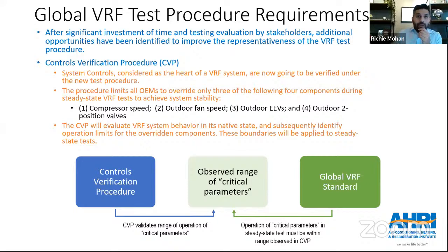And therefore, before we run a steady state test, we will run a pre-steady state procedure, which is the CVP, in which we leave the entire system in its native state, without any compressor speeds locked out, without locking the outdoor fan speeds and the expansion valves. We just let that system be in the test chamber, and all we are going to modulate is the test chamber temperature, so basically your outdoor ambient temperature, and see how the various parameters of that particular system behave.